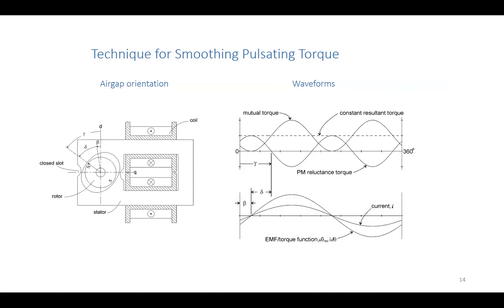And so obviously the higher the bandwidth that you require, the higher your converter volt ampere requirements are to be able to achieve that, because you need to apply a higher voltage to the electromagnet. So you want the converter volt ampere requirements to be feasible as well. You don't want to need giant converters with really, really high voltages. So as part of the design process, you're designing so that it is economic as well.